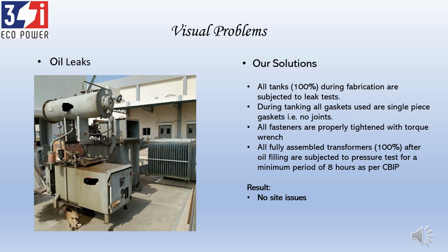So even if it costs a little more, we use single-piece gaskets - a single-piece rectangular gasket for cable boxes, or single-piece gaskets for Buchholz relay flanges, cable boxes, bushing pockets, and so on. This gives a good appearance to the transformer and avoids all leaks. That's one important thing we do.